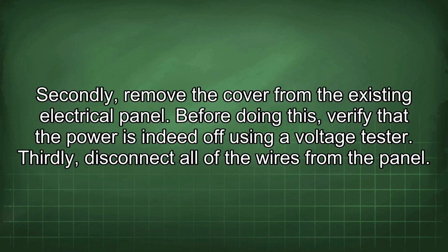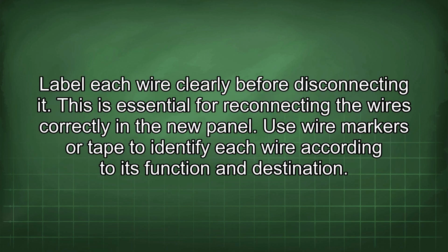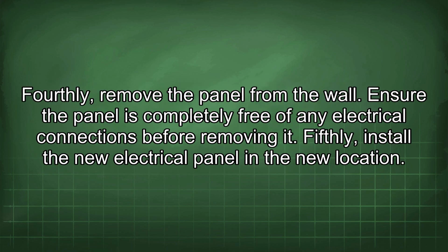Thirdly, disconnect all of the wires from the panel. Label each wire clearly before disconnecting it. This is essential for reconnecting the wires correctly in the new panel. Use wire markers or tape to identify each wire according to its function and destination. Fourthly, remove the panel from the wall. Ensure the panel is completely free of any electrical connections before removing it.